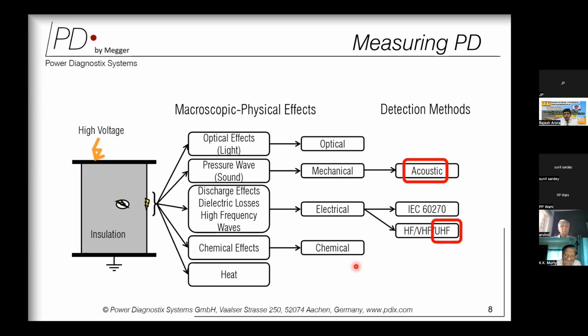The first is acoustic. Now, the acoustic measurement method can be used for detection of certain deformations in partial discharge, but acoustic cannot be used for continuous 24/7 monitoring. The reason: it is susceptible to noise, can be easily disturbed, and some specific kinds of measurement tools and noise elimination techniques have to be used. It cannot be implemented for continuous monitoring, and it is limited to only manual measurement with some portable instruments.